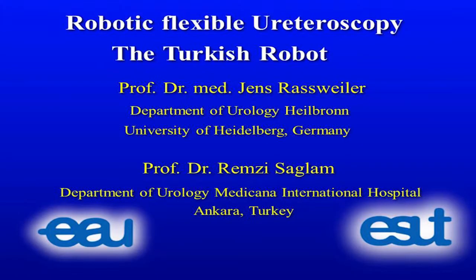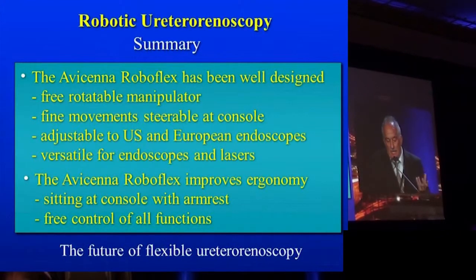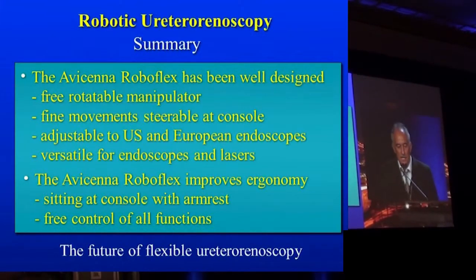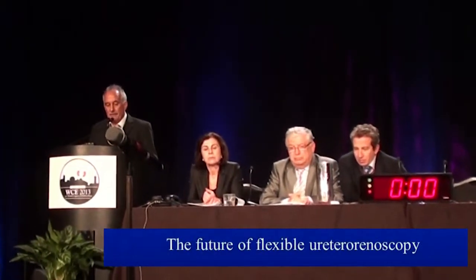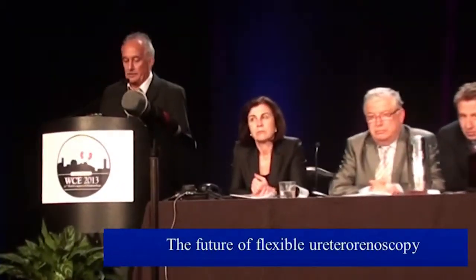We are talking about flexible ureteroscopy or retrograde intrarenal surgery. In summary, the Avicenna Roboflex has been, in my view, a very well-designed instrument. It's a freely rotatable manipulator with fine movements, steerable at the console, adjustable to US and European endoscopes, versatile for endoscopes and lasers. The Avicenna Roboflex improves ergonomy significantly — sitting at the console with an armrest, free control of all functions — and in my view, it's really the future of flexible ureteroscopy.